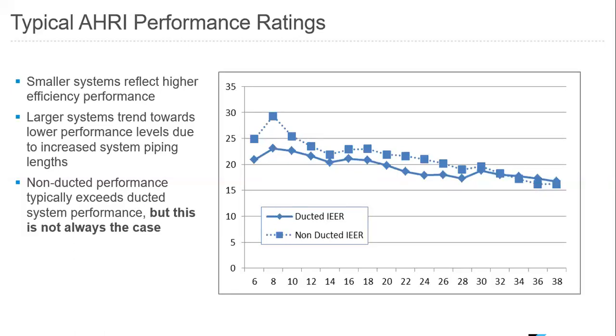So you'll see that typical ratings for non-ducted systems starting at 6 tons or higher. Then at 8 tons, they kind of peak. We're right around 30 IEER. IEER is the integrated efficiency ratio. That actually truly defines the performance, looking at specific performance points for each size system, all the way from 6 tons up to 38 tons.